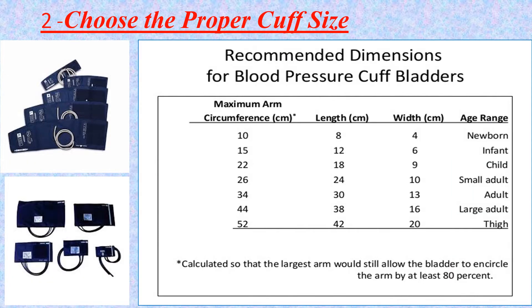Before performing the measurement, you need to select a suitable cuff. The proper cuff size is important: you cannot use an adult cuff on a small child, and you cannot use a pediatric cuff on an adult or a large person. Using the wrong cuff size will give you wrong measurements. You are not required to memorize all the sizes, but you need to know how to choose the proper cuff size.